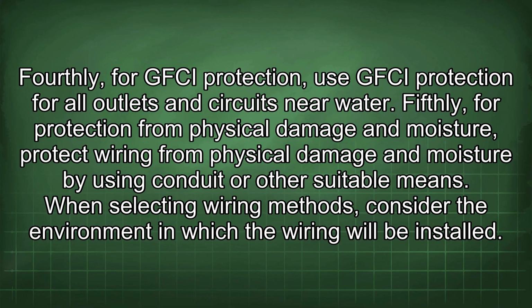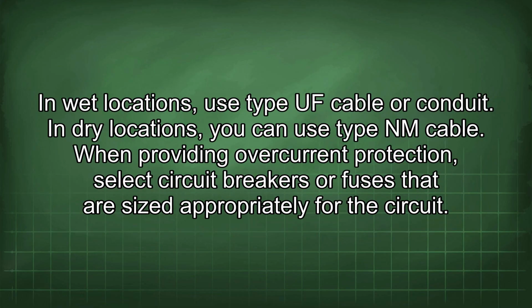Fifthly, for protection from physical damage and moisture, protect wiring from physical damage and moisture by using conduit or other suitable means. When selecting wiring methods, consider the environment in which the wiring will be installed. In wet locations, use type UF cable or conduit. In dry locations, you can use type NM cable.